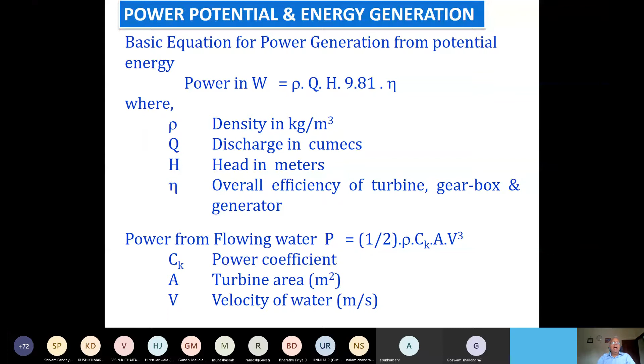Gross head is the vertical distance, not the longitudinal distance, but the vertical difference between the open surface upstream and downstream. We also have to subtract the losses that happen in the water systems through the trash rack, pipe friction, bends, valves, and the exit losses - all of that becomes my losses.